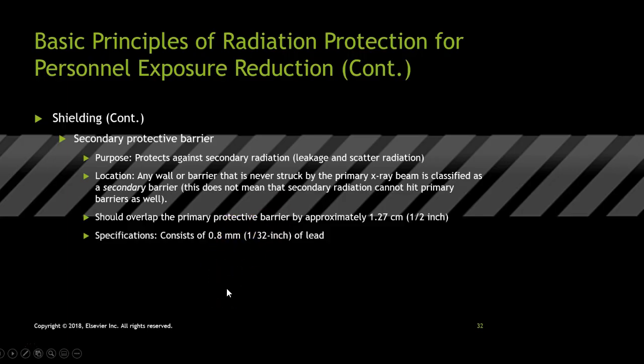Okay, the secondary protective barrier. Its purpose is to protect against secondary radiation. And remember, secondary radiation is anything other than primary. Secondary includes leakage and scatter radiation. The location of the secondary barrier is any wall or barrier that is never struck by the primary X-ray beam. So that could be every other wall, every door, every window in that X-ray room. All of those other surfaces are secondary barriers. The secondary barrier should overlap the primary one by approximately half an inch, and they do, inside the drywall. The specification at 120 kVp is 0.8 millimeters of lead. So that's half of what the primary needs to be.